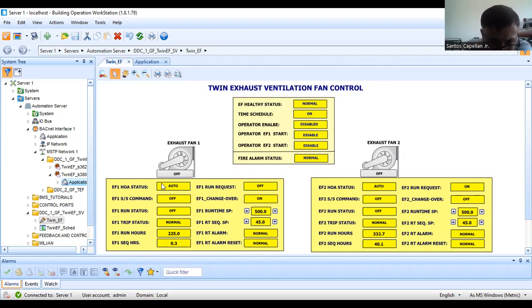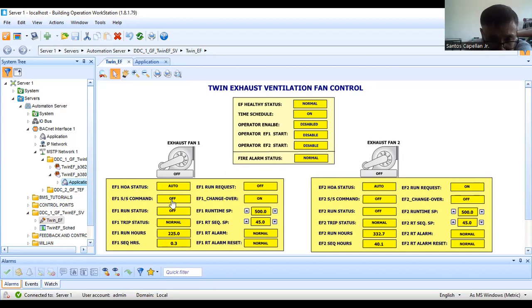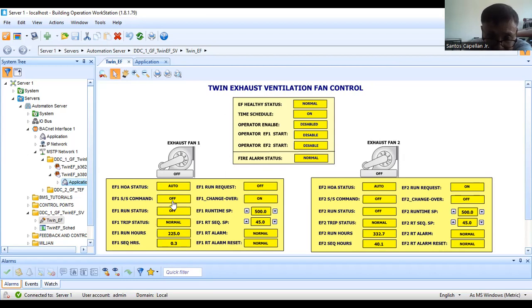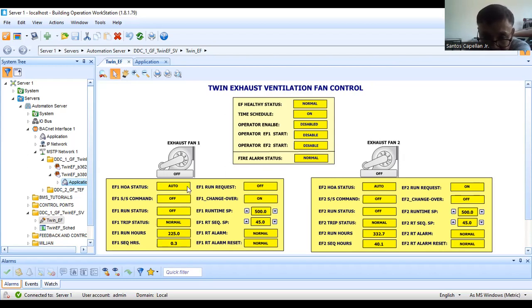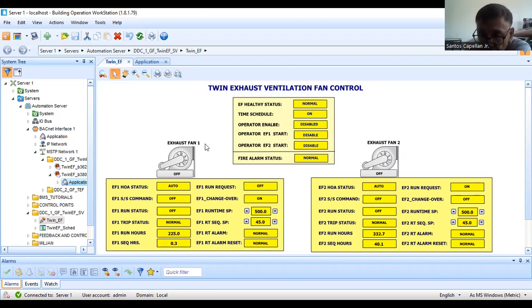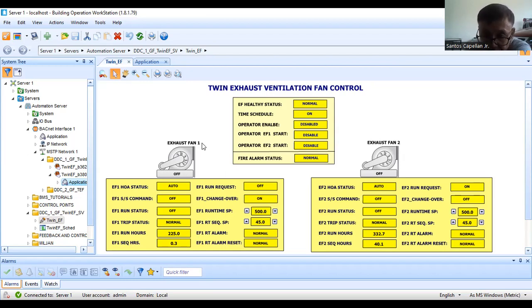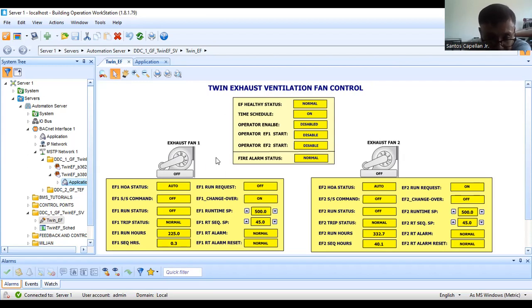These are the normal monitoring points: auto selector switch position, then the start/stop command of our control logic program. If it is in automatic, this point is the control. Then run status, we are monitoring the run status. What is missing here is the airflow control. For the airflow control, that is the last part of this series. I will try to prepare the script program for that.